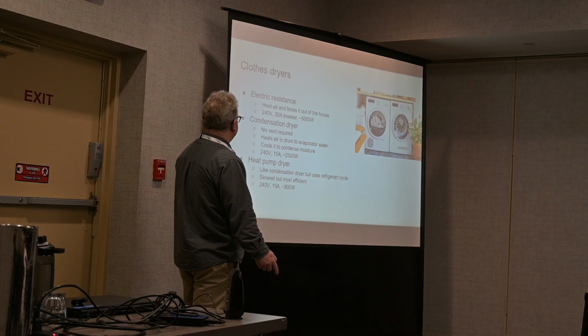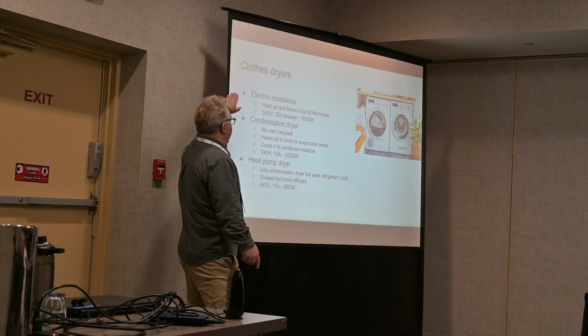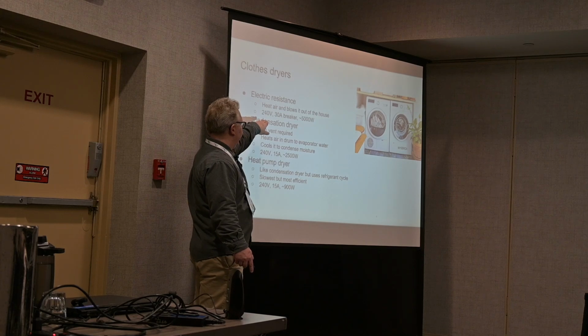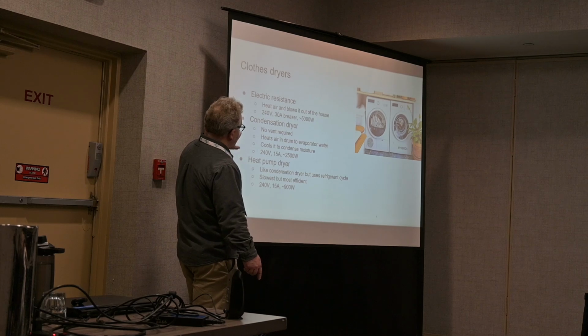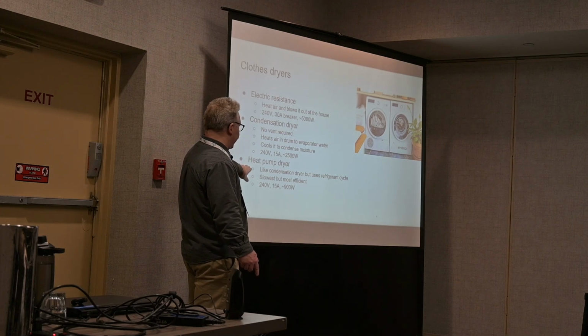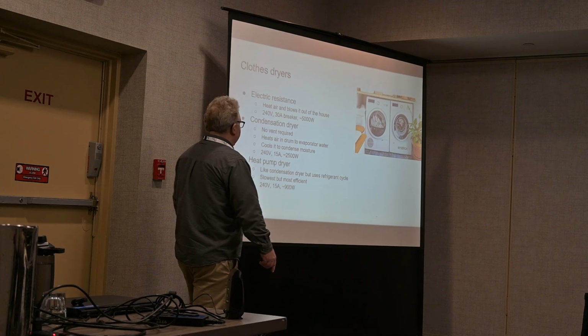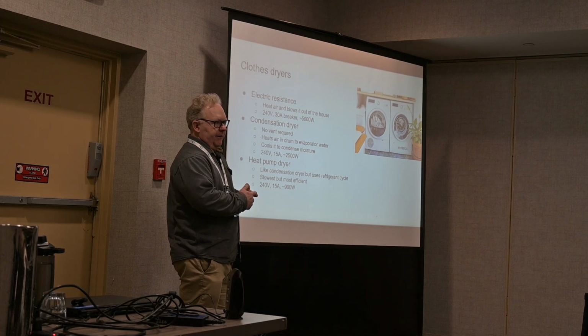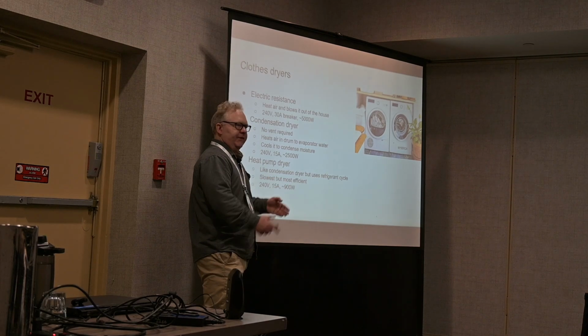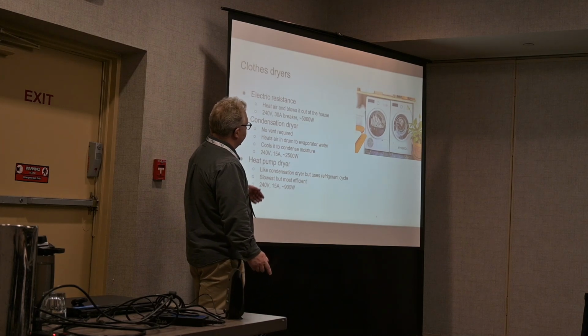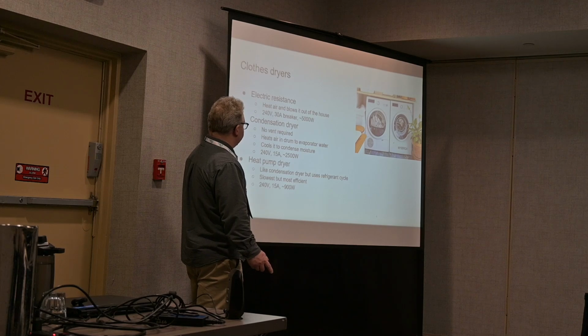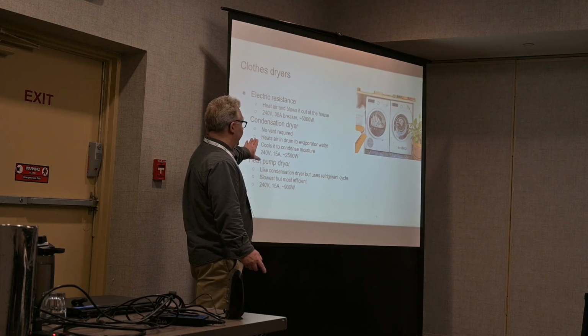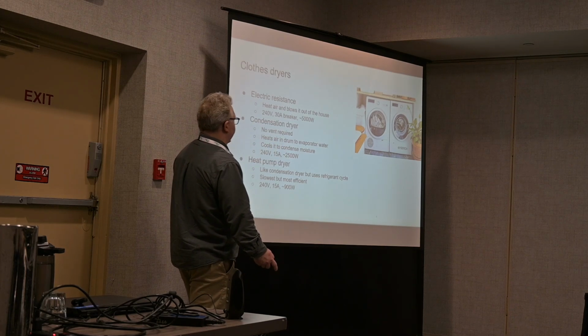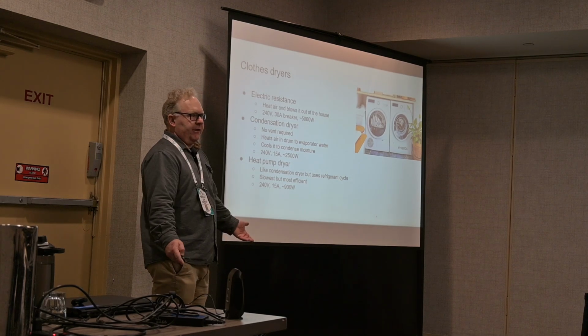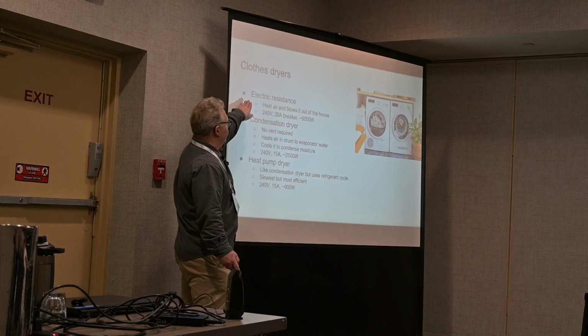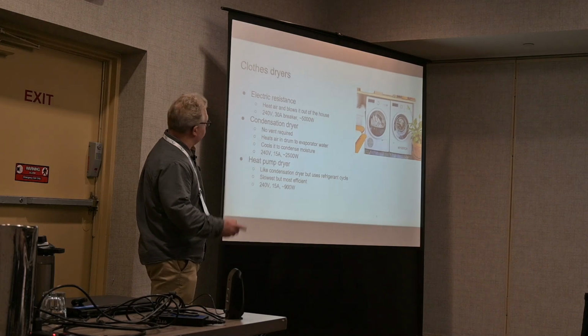Clothes dryers, this is sometimes the last thing that we need to electrify so that we can shut off the gas meter. Our standard electric dryer is going to take a 30 amp breaker and draw about 5,000 watts. There are also condensation dryers and heat pump dryers that have much lower wattage requirements. Another advantage of these is that they don't require a vent. So in cases where, say, it's an interior of an apartment, for example, these don't require a vent. They can just drain the water into a plumbing drain. The disadvantage is that they're more expensive to buy and they're a lot slower. So they're definitely not for everybody. And clothes drying is rarely a big part of someone's overall energy bill. So where the panel and the house will support it, probably this is what most people are going to end up choosing.